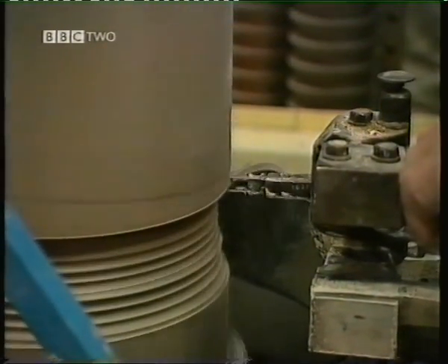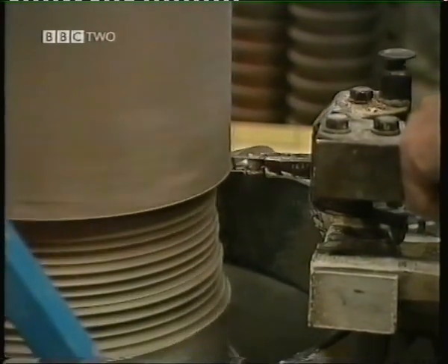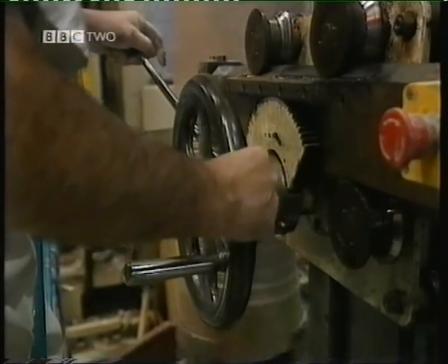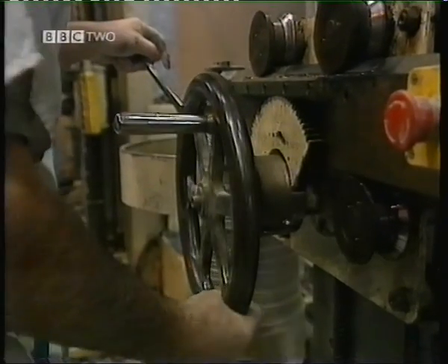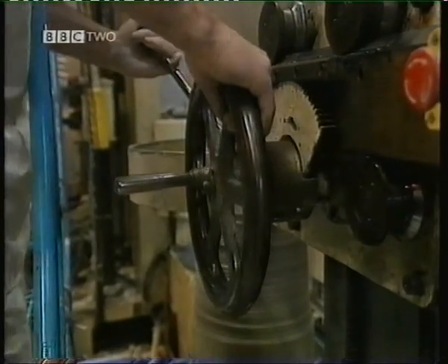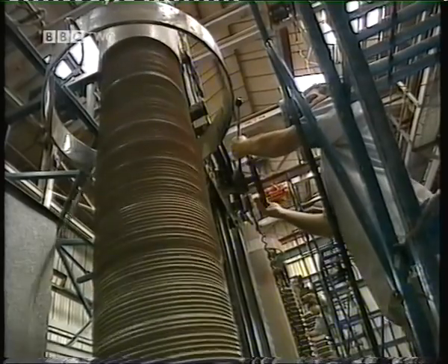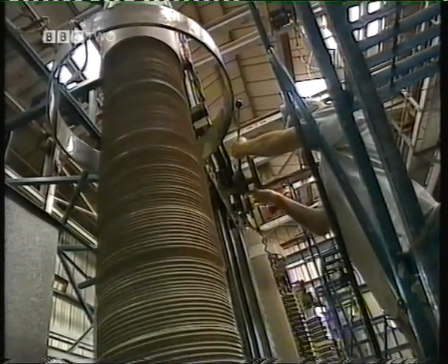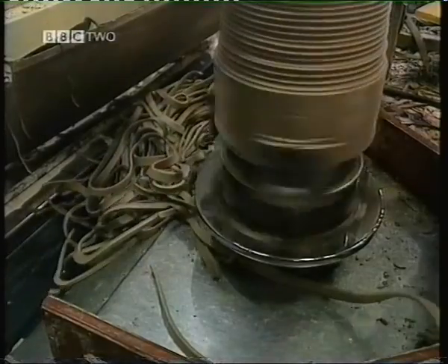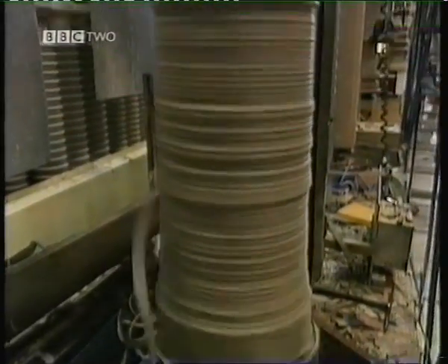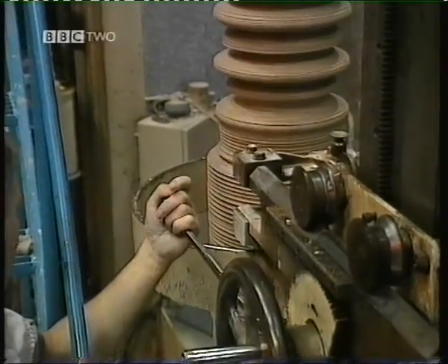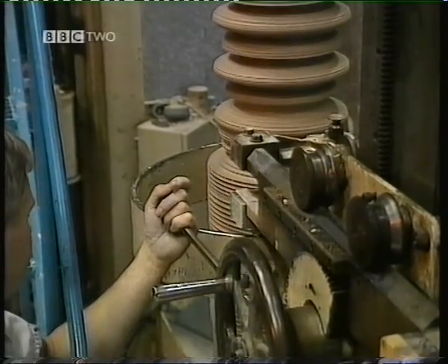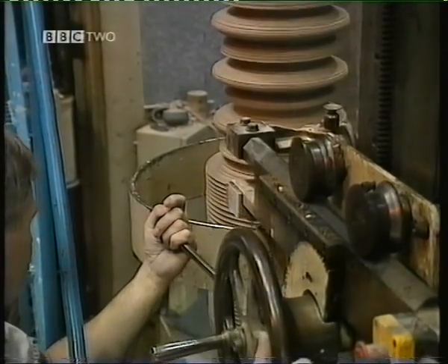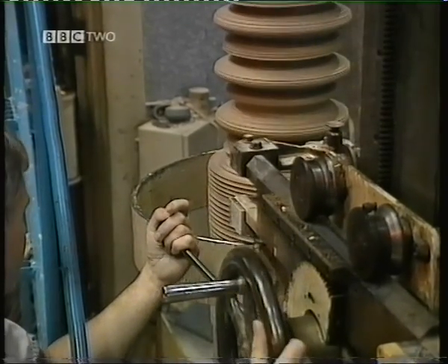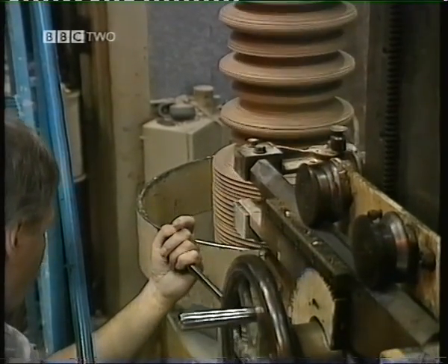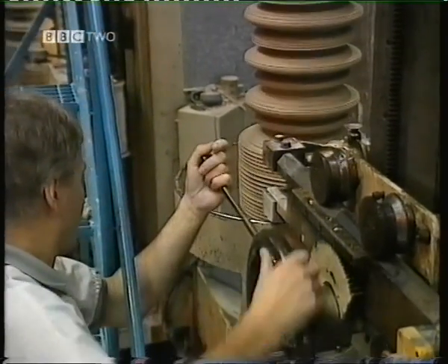It's here that the shape of the insulator begins to emerge as the excess material is removed in ever finer stages. The characteristic shape, the ridges are called sheds, ensures that a good length of surface exists to spread the electrical stresses along. When the system experiences a fault voltage, the tightly bound electrons in the molecules of the bulk ceramic material aren't the ones most likely to get released. It's those in the surface deposits and in the surrounding air which yield and lead to flashover.